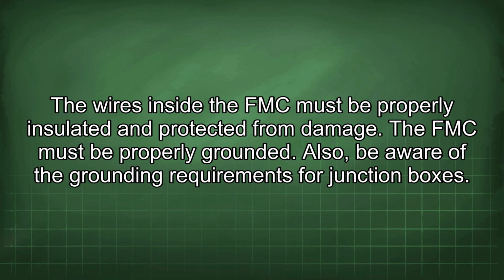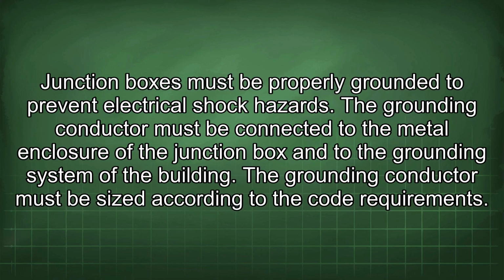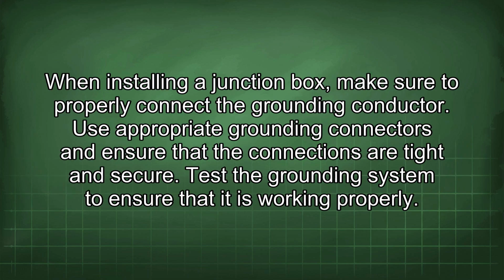Also, be aware of the grounding requirements for junction boxes. Junction boxes must be properly grounded to prevent electrical shock hazards. The grounding conductor must be connected to the metal enclosure of the junction box and to the grounding system of the building. The grounding conductor must be sized according to the code requirement. When installing a junction box, make sure to properly connect the grounding conductor. Use appropriate grounding connectors and ensure that the connections are tight and secure. Test the grounding system to ensure that it is working properly.